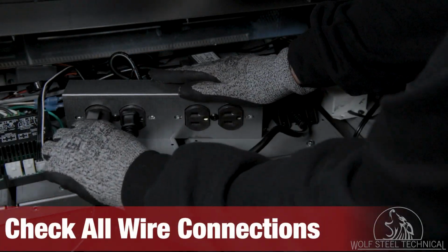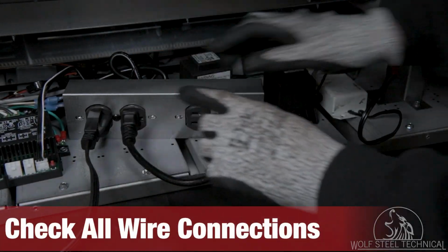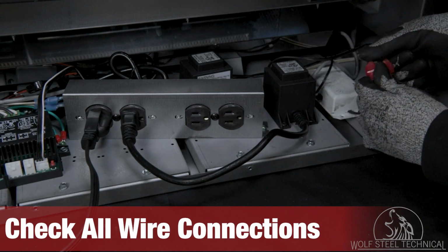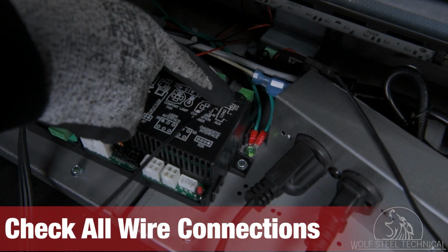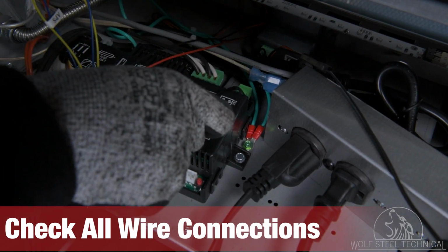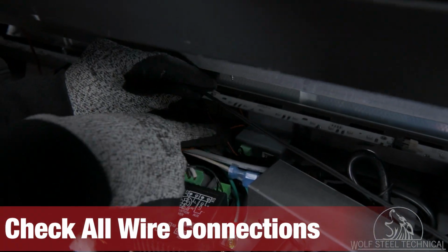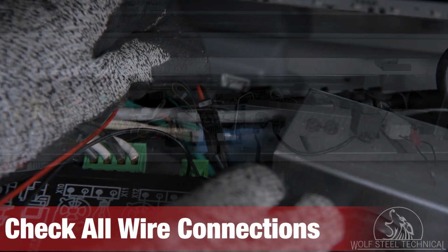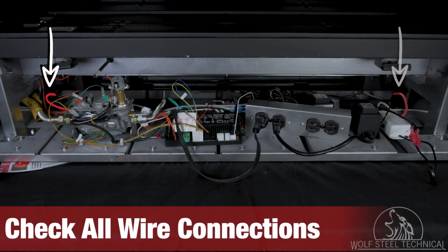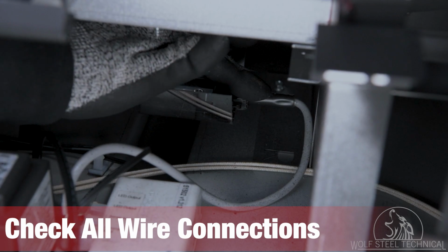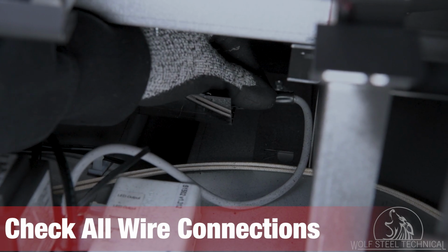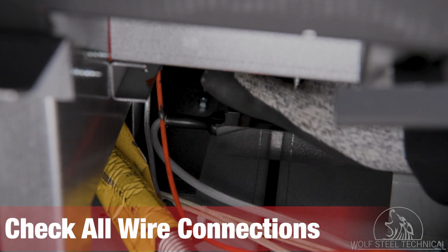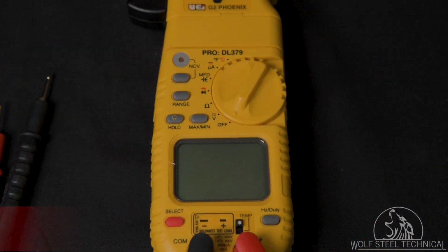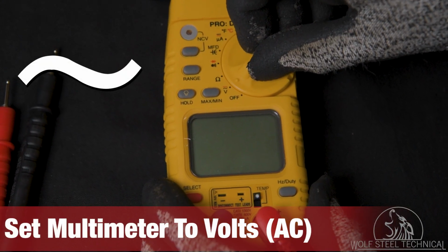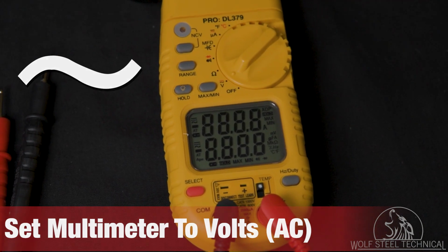Begin by checking that the transformer is plugged into the main junction box and connected to the LED control. Check that the LED controller is connected to the X13 auxiliary on the control board and the Bluetooth module. Next, ensure that the wires on either end of the LED strip are connected correctly. Ensure both ends are pushed in fully and the wire is correctly aligned with the LED strip so all pins are in contact. Once all connections have been checked, set your multimeter to volts, AC.